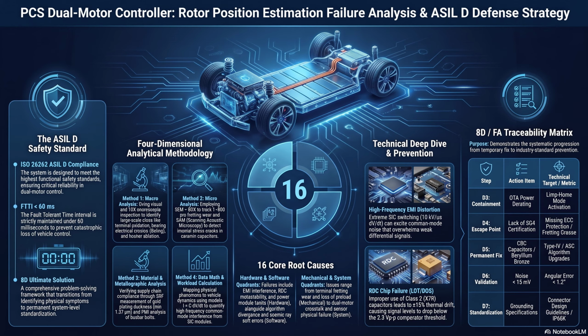That brings us to the final layer, Dimension 6, safety and extreme response. This dictates exactly how the software is allowed to behave when a catastrophic, unrecoverable error is verified. Right. How do we stop the software from detonating the inverter with an uncontrolled generation event? The defense grid strictly prohibits the three-phase freewheeling shutdown at high speeds, because opening the switches is a death sentence for the SiC modules. Instead, the dual-core lockstep processor executes a precisely timed active short circuit, or ASC. Shorting the phases together on purpose.